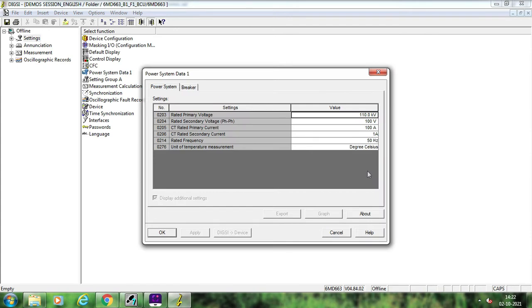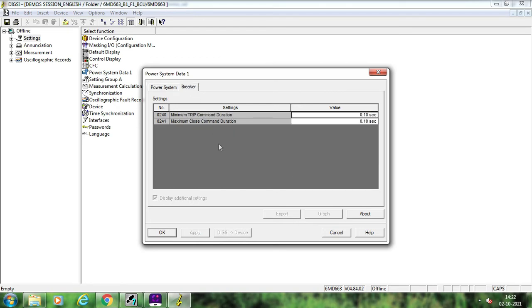In today's session we will start with Power System Data 1. Inside Power System Data 1, the voltage and current of the primary and secondary of the CVT and CT are required to be entered. This depends upon your system — for example, in this case this is a 400 kV by 110 volt CVT and the CT ratio is 2000 by 1, and the rated frequency is 50 Hz. Another important setting is the breaker settings: the minimum trip command duration and maximum close command duration, which by default are 100 milliseconds for both tripping and closing.